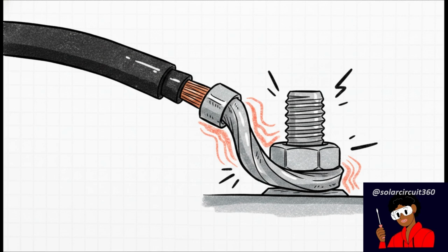Think about the mechanical strain risks. If your inverter mounting or cable routing is putting physical stress on those DC terminals, it's going to twist the cable lugs. And that mechanical strain translates into micro movements at the connections over time. Maybe it's subtle vibrations, or maybe it's just the natural expansion and contraction from heat cycling. But that micro movement slowly loosens the connection, dragging you right back into that nasty cycle of resistance buildup and unseen thermal degradation we just talked about. I mean it, your electrical safety literally depends on your mechanical stability.